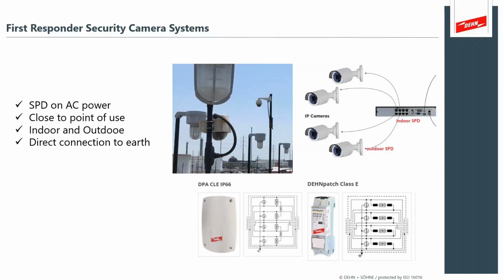First responder security camera systems, and this is, of course, the cameras are going to pretty soon outnumber citizens. You can see that the camera has an outdoor portion of the apparatus that needs to be protected at the actual camera end, and as importantly, or more importantly, at the indoor end of the power over Ethernet circuit, where it needs to be applied on the router input before you get through the device. So these are considered series devices, where that protects the circuit in series with the operation.